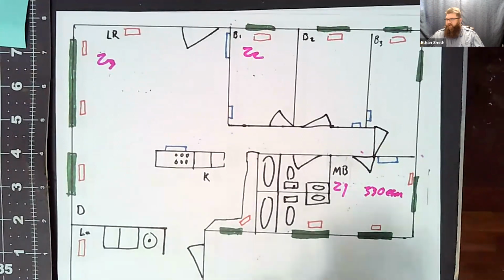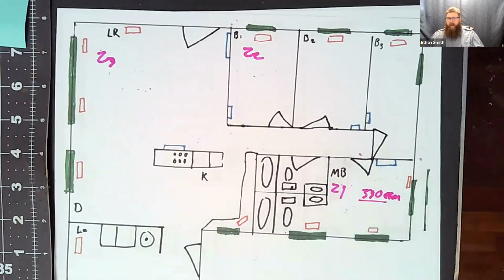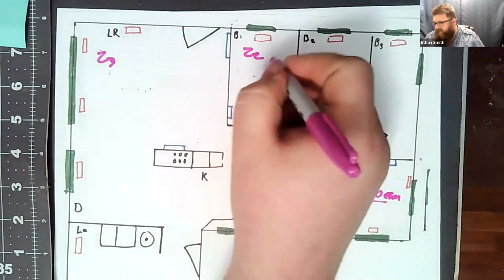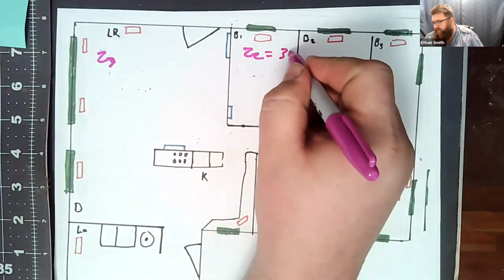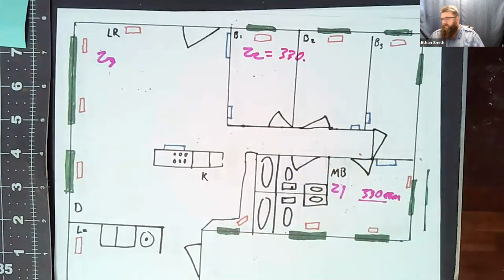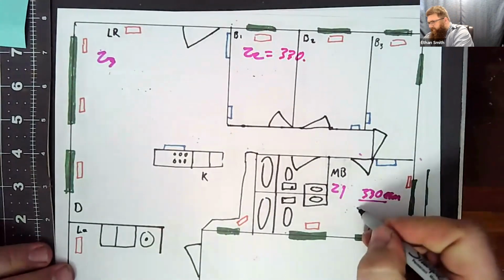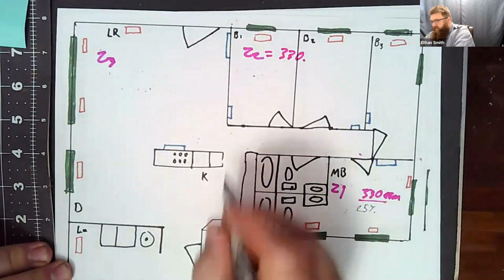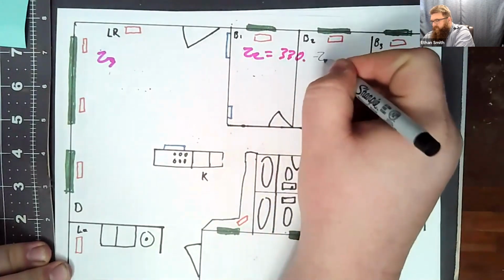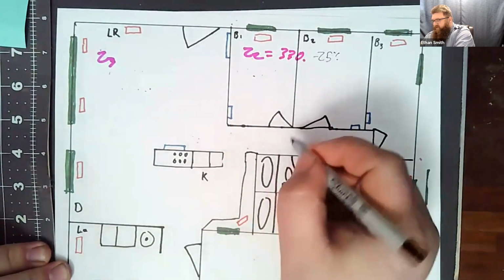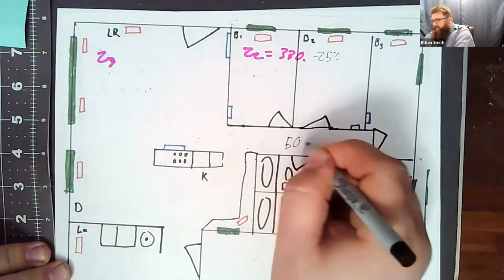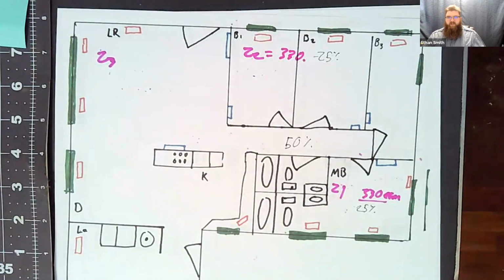Okay. I can turn that unit down to where it will exactly match the capacity of that zone. I have no excess air problem at that point, guys. If my zone 2 turns on while zone 1 is running and it needs another 330 CFM, my outdoor unit will go from 25% up to 50%. And it will give me 660 CFM. No excess air problem.